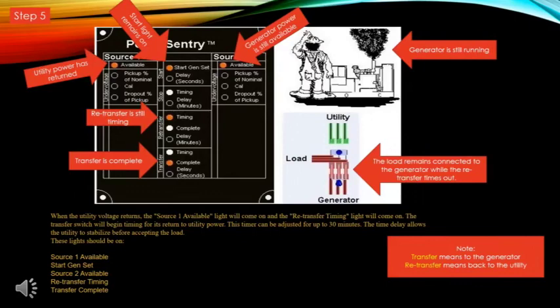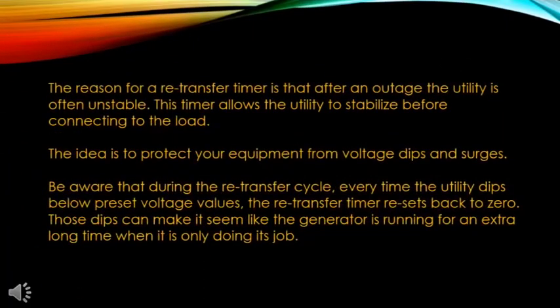Note: transfer means electrical power transferred to the generator; retransfer means electrical power transfers back to the utility. The reason for a retransfer timer is that after an outage, the utility is often unstable. This timer allows the utility to stabilize before connecting to the load, protecting your equipment from voltage dips and surges. During the retransfer cycle, every time the utility dips below preset voltage values, the retransfer timer resets back to zero. Those dips can make it seem like the generator is running for an extra long time when it's only doing its job.